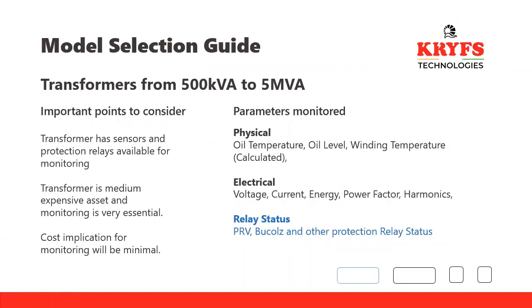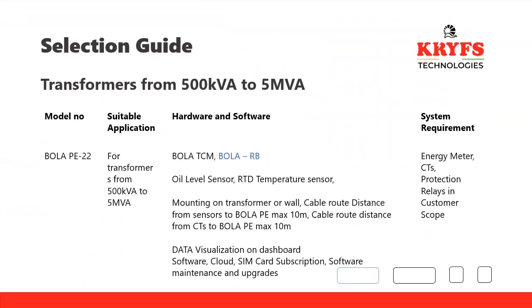Second model, what we offer is from transformers from 500 kVA to 5 MVA. In such type of transformers, the sensors are already installed. Many of the sensors are installed on the transformer. Transformer is a medium expensive asset and monitoring is very essential. Cost implication for monitoring will be minimal. In such kind of transformer, normally all other parameters are same as before, but we additionally monitor PRV, Buchholz and other protection relay status. Okay.